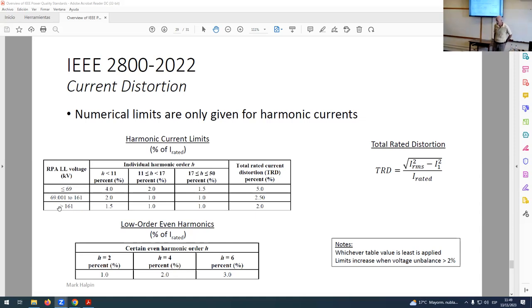This is a limit of voltage imbalance for the individual. Well, so the generation equipment has a limitation of unbalance of injection of current. Mm-hmm. Because you can produce the imbalance if you inject unbalanced current. That's right. So there exists a limit for the people that inject current that they must be balanced. Yeah, but again, today, in the IEEE arena, we don't yet have an unbalanced document.